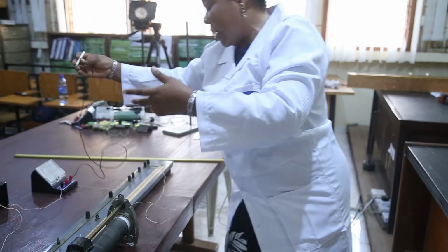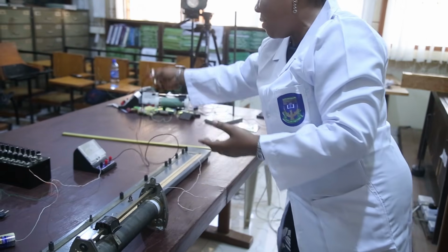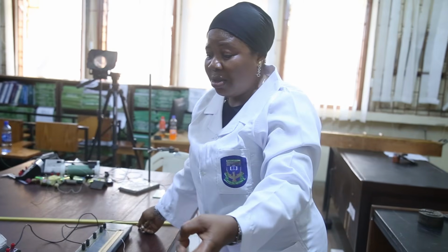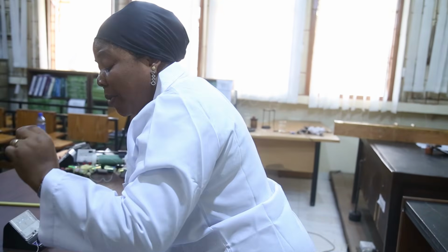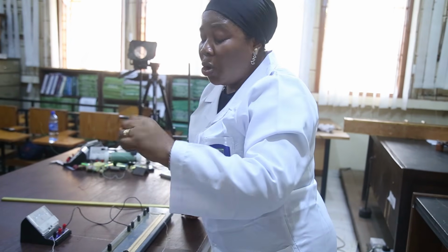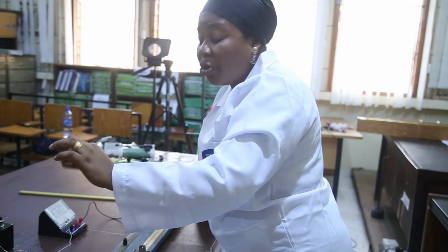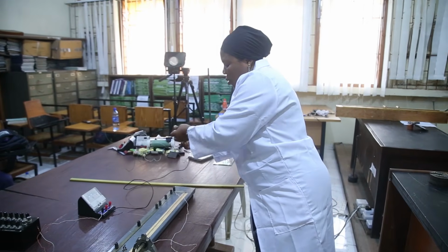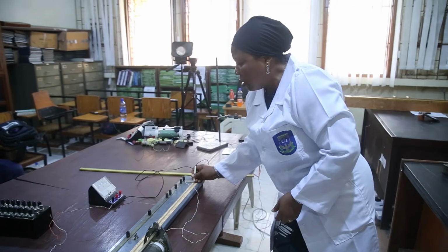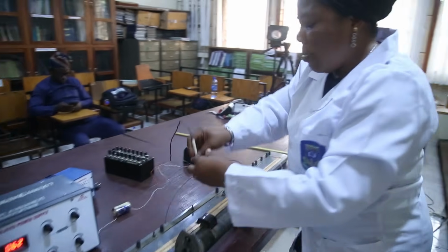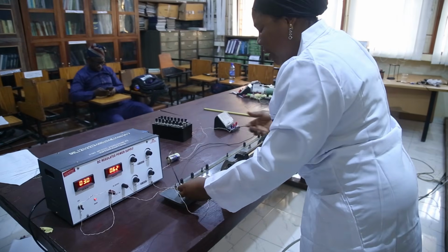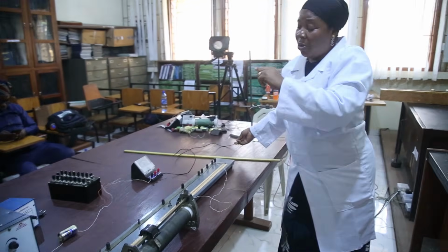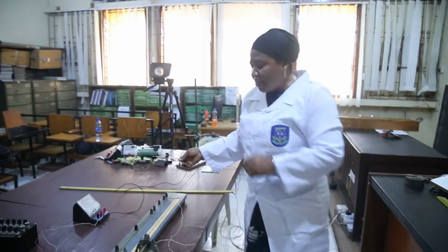All you need to do is check again and see where you're going to have the balance point. But before you check, you first of all ensure again that it's deflecting, to be sure that there has been no disconnection from the terminals of your battery. So take it on this point. See your deflection. Remember that the protective resistance is no longer there. Put it to this point also. So we now repeat what we did when the protective resistance was there, to get the balance point.